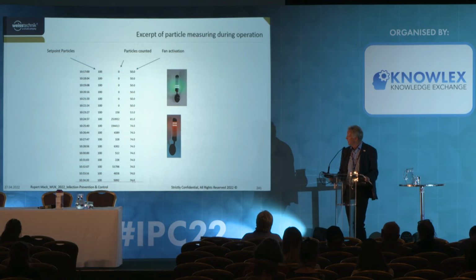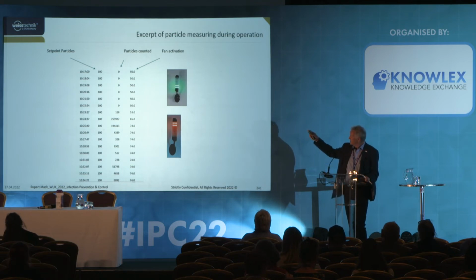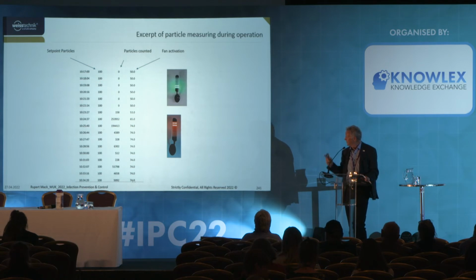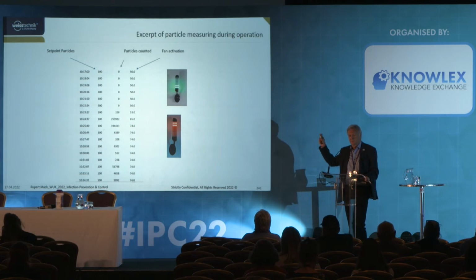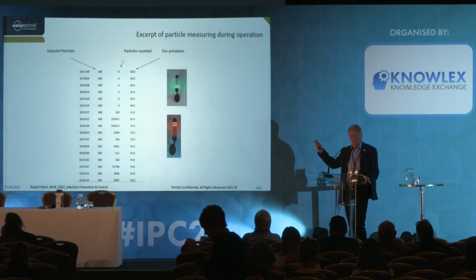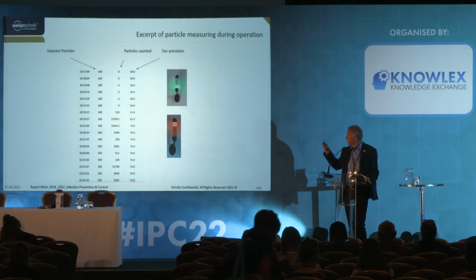So now we say, okay, we want to achieve class 5, and we made measurements close to the instrument table, and the measurement shows zero particles, and then there was a jump to 158 and 250,000, 190,000. This came with surgical smoke. No one can produce that many particles within 1 or 2 minutes.